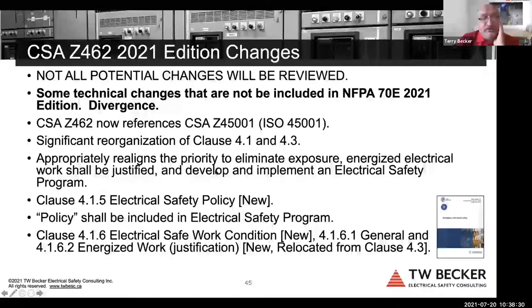So again, Z462, the conversation is the same. It's just instead of article, it's clause. So the changes that I've told you about are the same. I'm just going to point out a few different things that we did differently. We do align with the organizational changes from 70E, but now we're talking clause numbers. Again, the policy statement to eliminate, establish an electrically safe work condition. If you can't, then justification for energized electrical work.